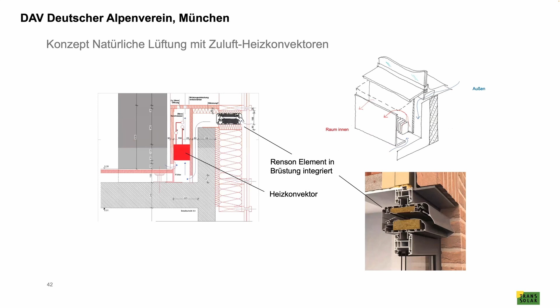We implemented it into the spandrel panel at the Brüstung, and then we added a heat exchanger for heating. So fresh air comes in, is preheated, and then enters the room. We have comfort ventilation without a big system. Interiorly, it's like a box integrated all along the facade, and that's about it - that's all the ventilation you have. Nothing, no ductwork at the ceiling. Ceilings are just the concrete ceilings, stripped of the suspended ceilings they had before, with some acoustic elements.